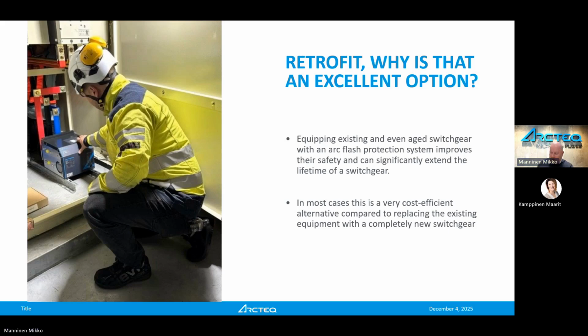I believe, and I know I share this opinion with many, that well-maintained switchgear can be used for years and years longer with proper maintenance. For example, circuit breakers - with protection, as I mentioned before, we have detection, protection, and mitigation. So for proper protection, you need a well-maintained and well-tested circuit breaker. That's one of the main things of the protection. All the other circuits as well - whether it's the Rogowski or the current transformer, it has to be tested and proven.